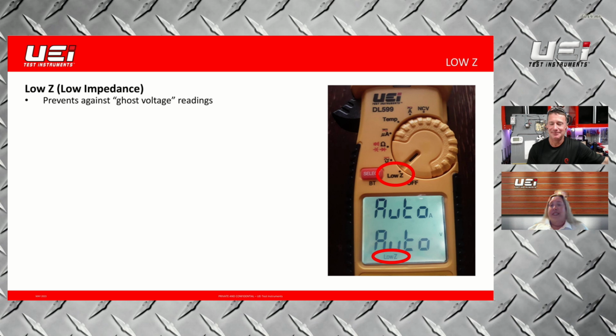So low Z is a setting on there, but we know, especially in today's world working in tight panels and those type of things, you're going to wind up with what we call ghost voltages. You're going to get an error reading on your meter, not the right reading. So we built in low Z on that meter series, and that low Z is going to filter out those ghost voltages.